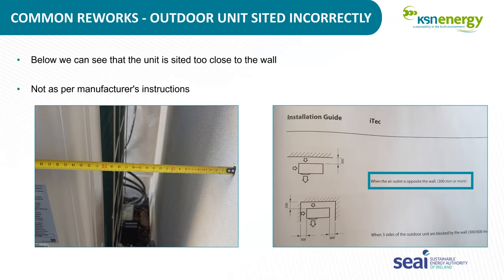The outdoor unit exchanges heat in the air and makes it into useful heat that can be exchanged into the home. If it's too close to a wall or someone puts a fence in front of it, it disrupts the airflow coming through the outdoor unit and limits the efficiency of the system. So we stress to everyone to make sure of this. An inspector will go out. They typically know what the tolerances are from the manufacturers, but they will reference it if they see one that's too close to a wall. Also, servicing needs to be considered. That's one thing we see when carrying out inspections on site.